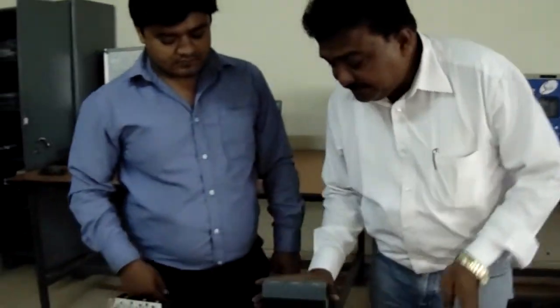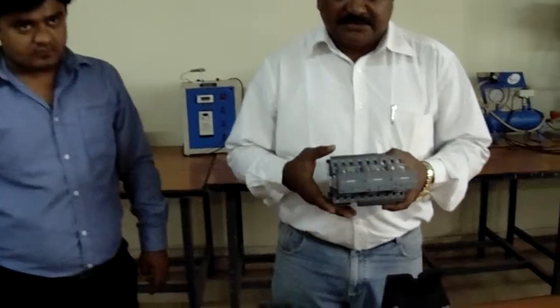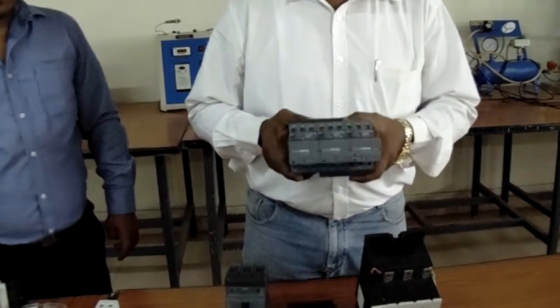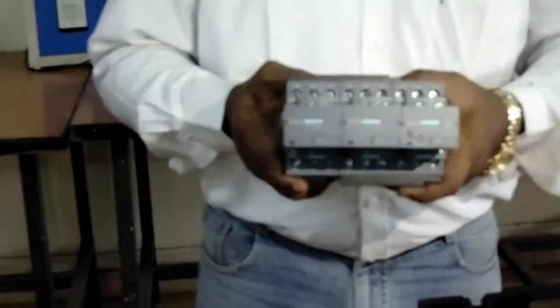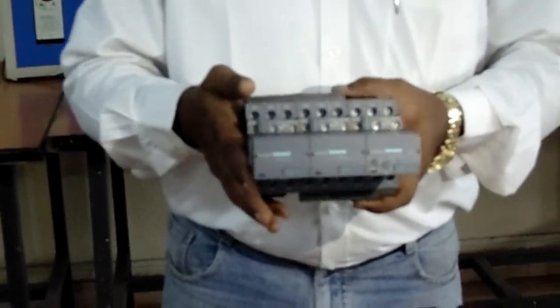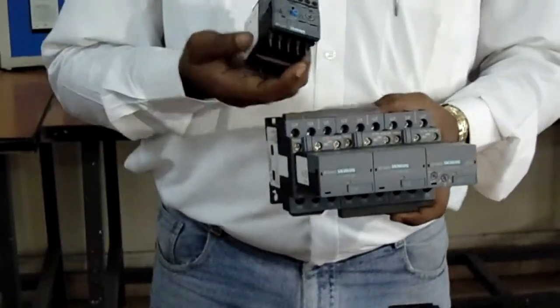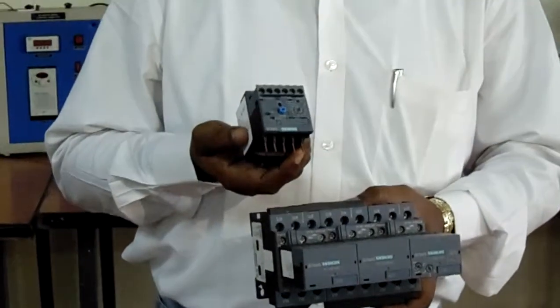Then comes the star delta starter. A star delta starter consists of 3 contactors. One line contactor, another one star contactor, and the third one is the delta contactor. This again, a combination of 3 contactors along with an overload relay, becomes a star delta starter.